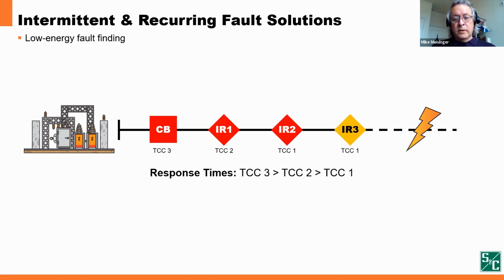Click. But when it is initiating this low energy testing, because the energy level is so low, it is not detected by IR2. Next click. And so IR3 only opens, IR2 remains closed. Next click. This process is repeated as you would in normal reclosing sequences until, next click, you eventually reach lockout. But because of low energy testing, we're not reinitiating this tripping of both IR2 and IR3 that was caused by the initial fault. So this enables us to increase the segmentation of the feeder where we can no longer achieve conventional time current coordination. Next slide, please.